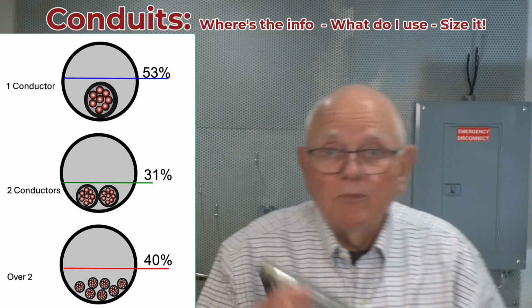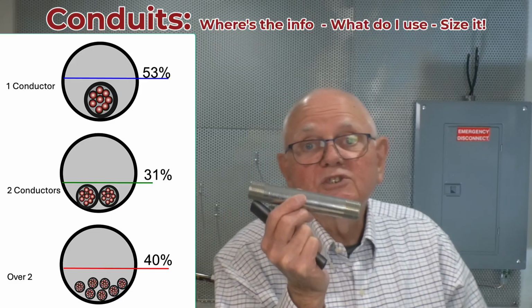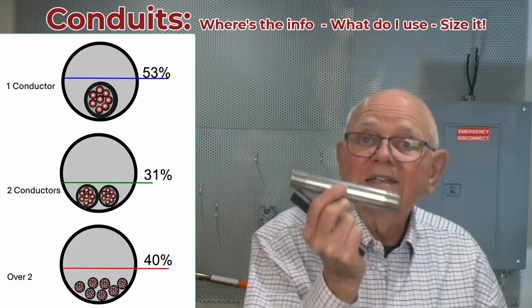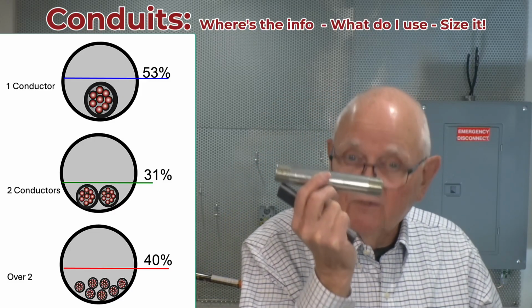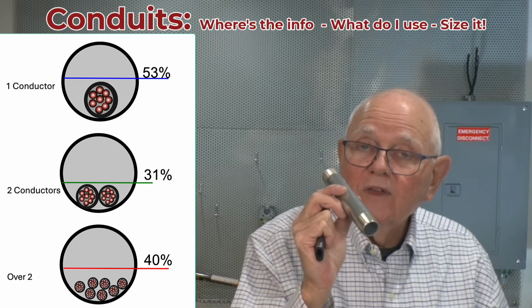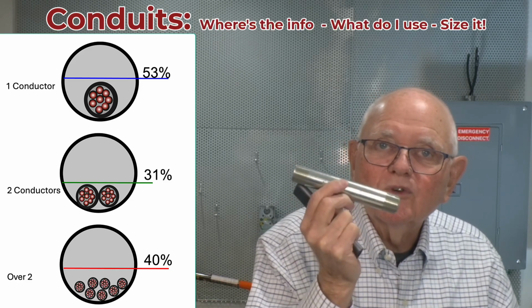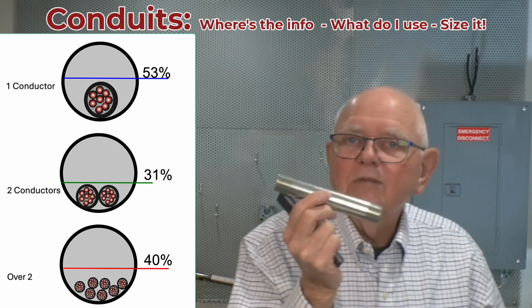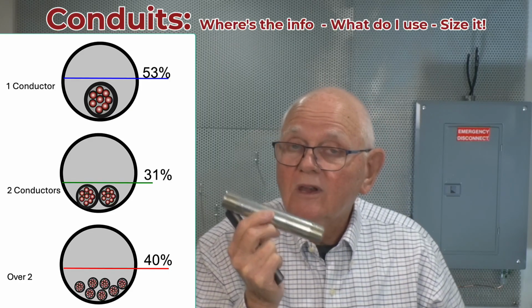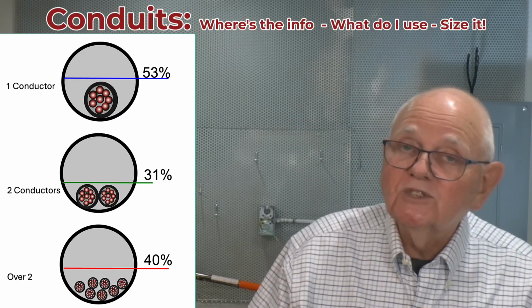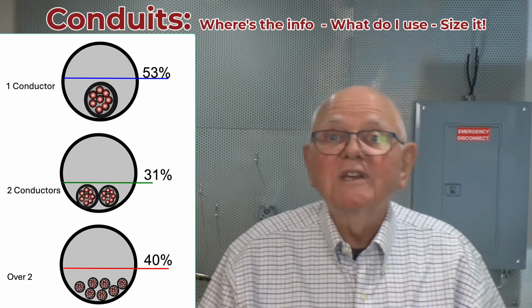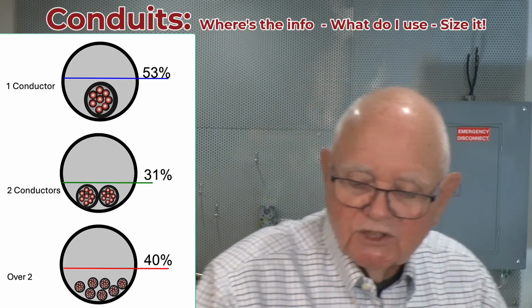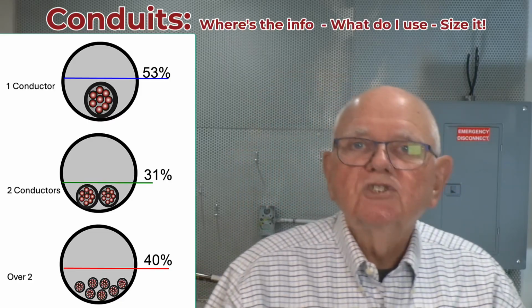If it is a nipple, which means it's 24 inches or less, I can fill that to 60% fill. Now, how do I know that? Because when I look at Chapter 9, Table 1, it's really a very short table, but it's got almost a whole page full of notes. So you want to read the notes on that. There's lots of information. So let's talk a little bit about Chapter 9, Table 1.